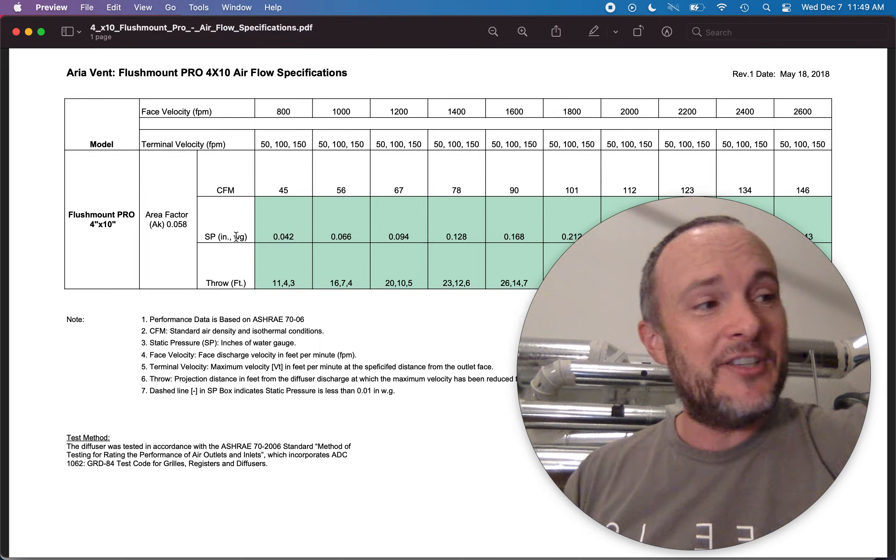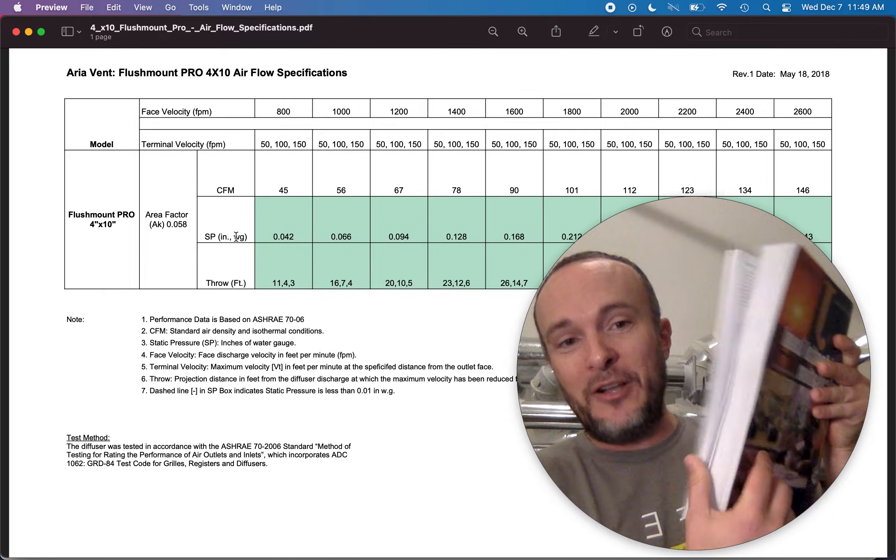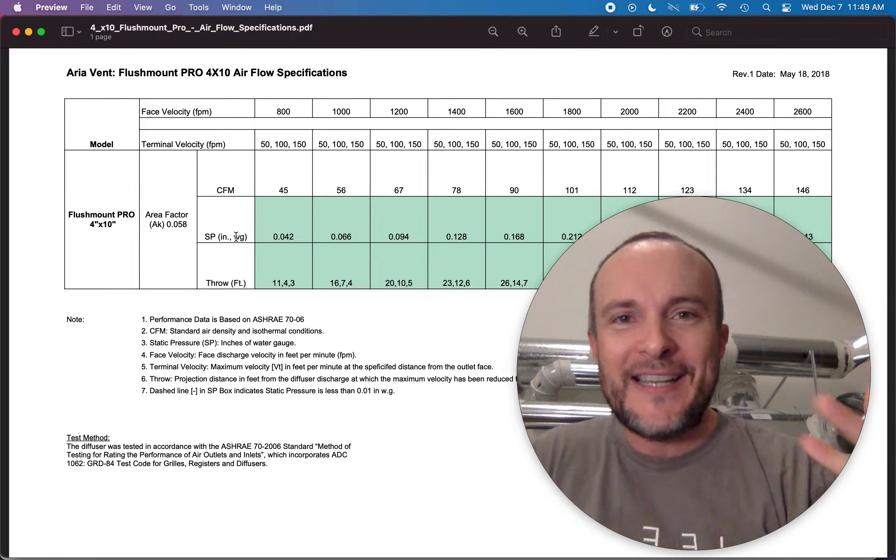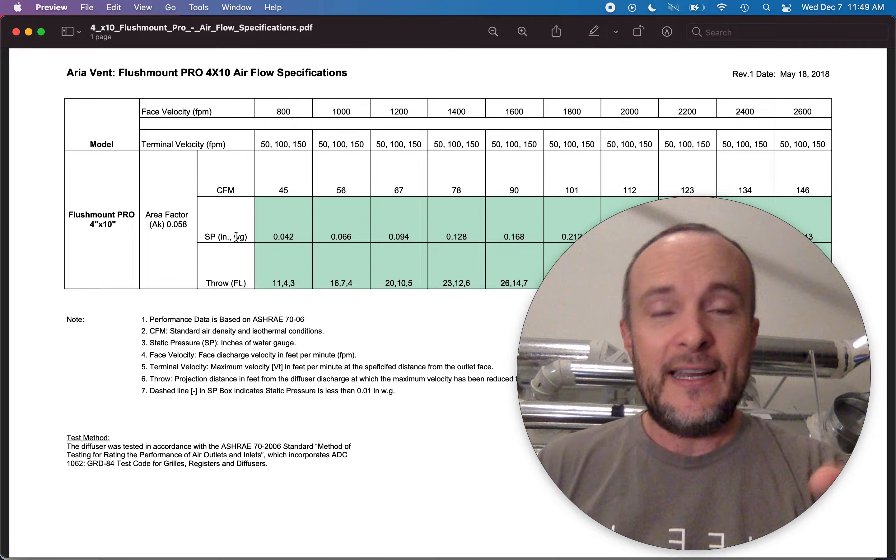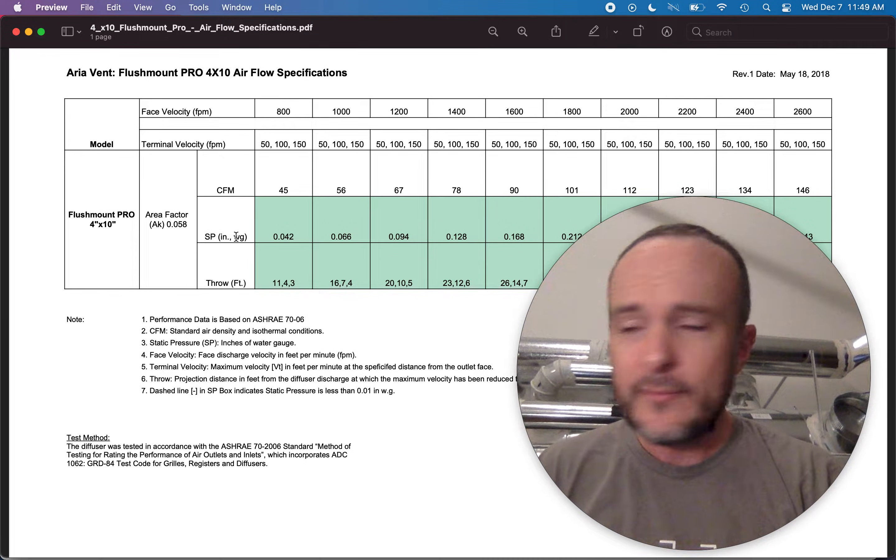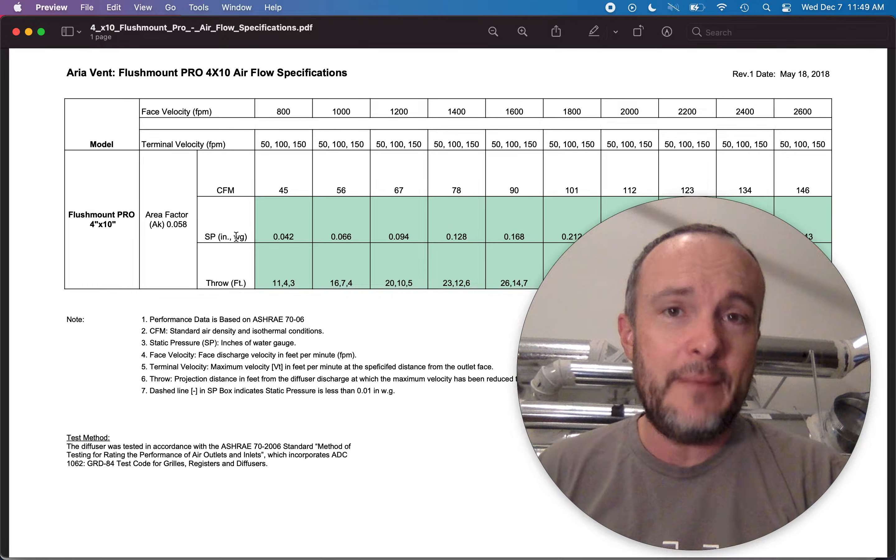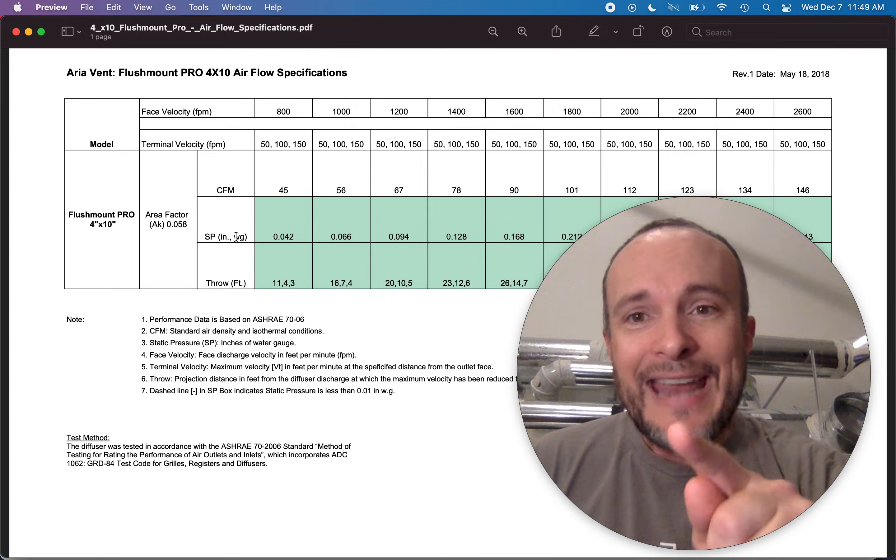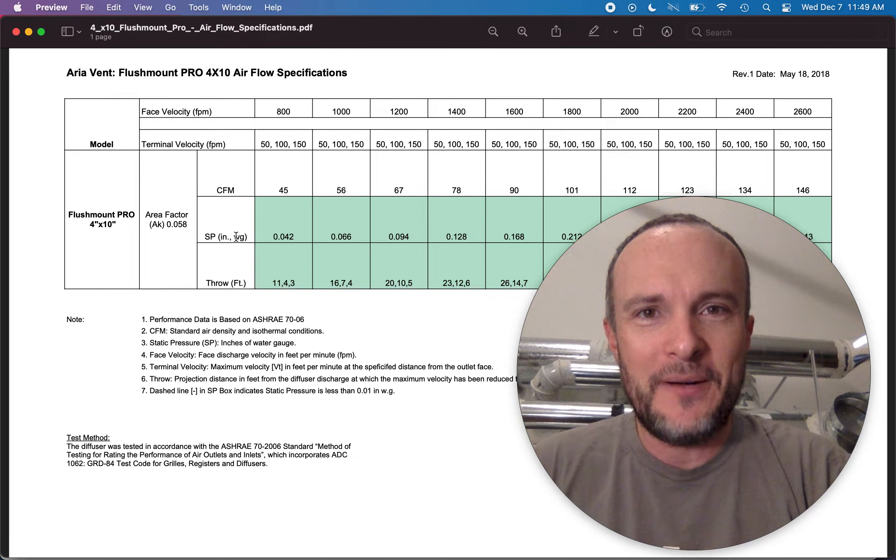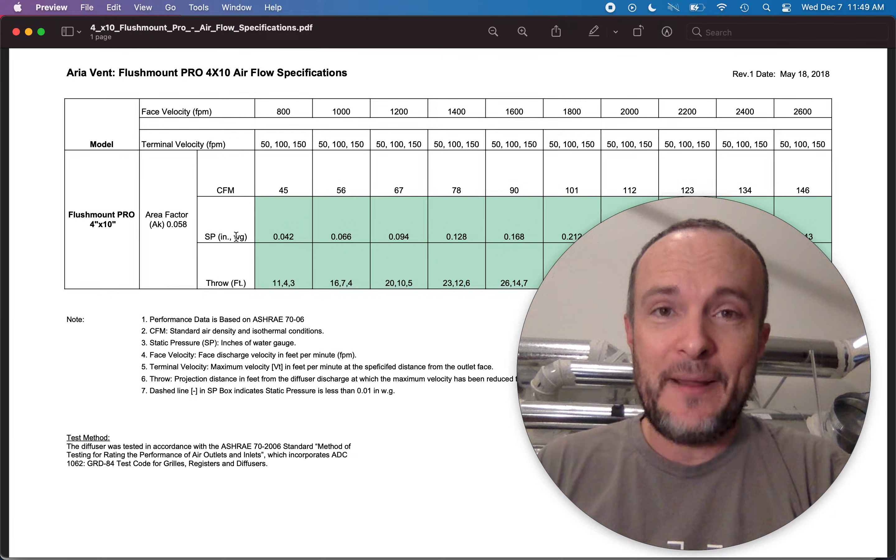Now what you should know is that in residential settings we aim for face velocities. If you read the ACCA guides for this, and this is Manual J, there's another manual called Manual T which is also just a manual for how to design residential HVAC systems. And the ideal velocity coming out of the face of one of these grills in a supply setting is going to be about 500 to 700 feet per minute. They're showing 800 to 2600 feet per minute in this chart. That is insanely high.